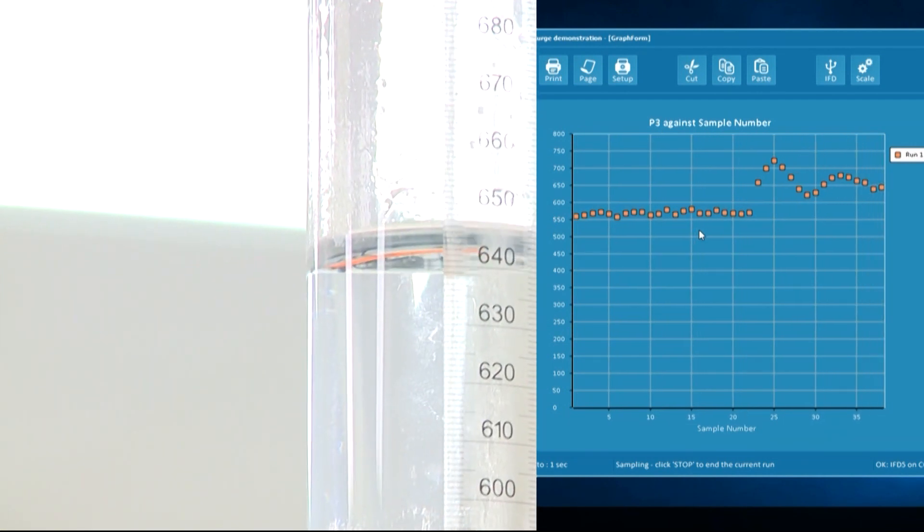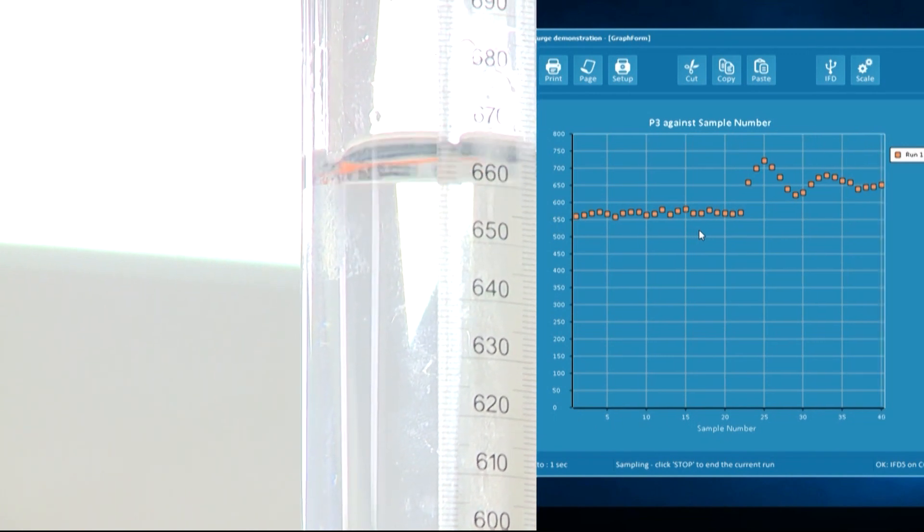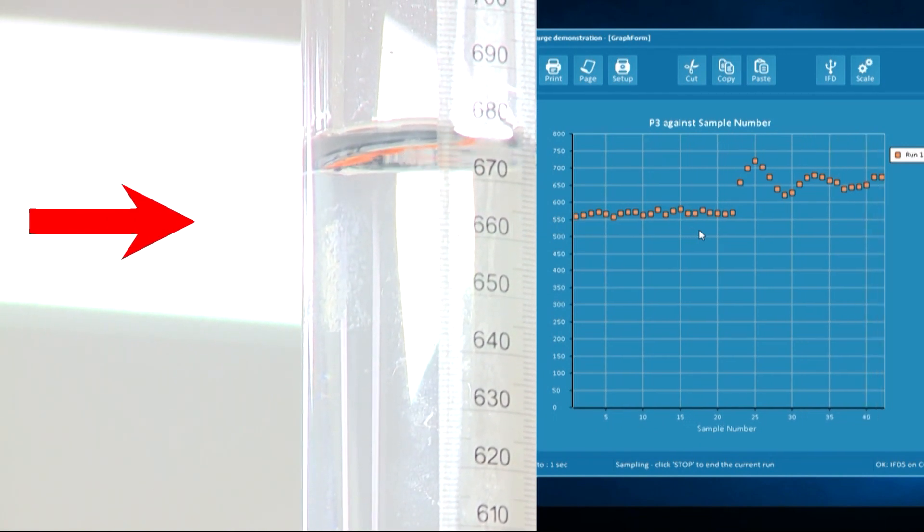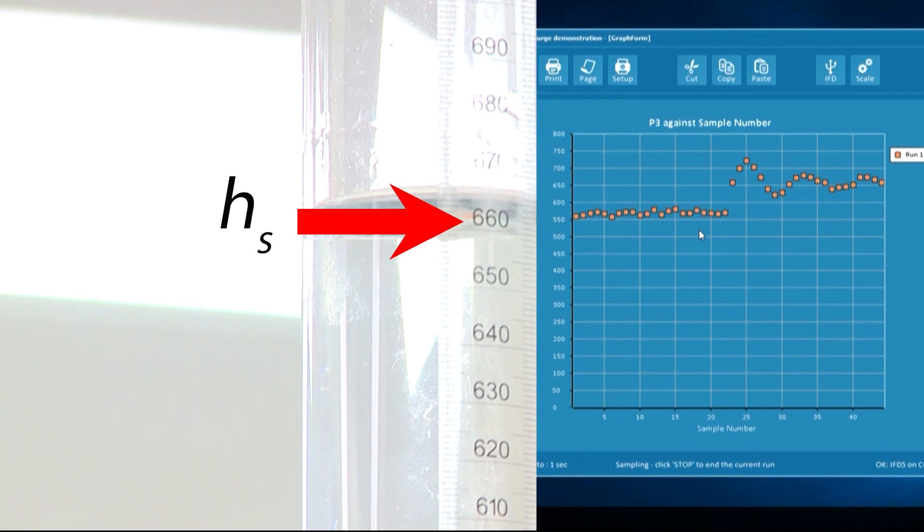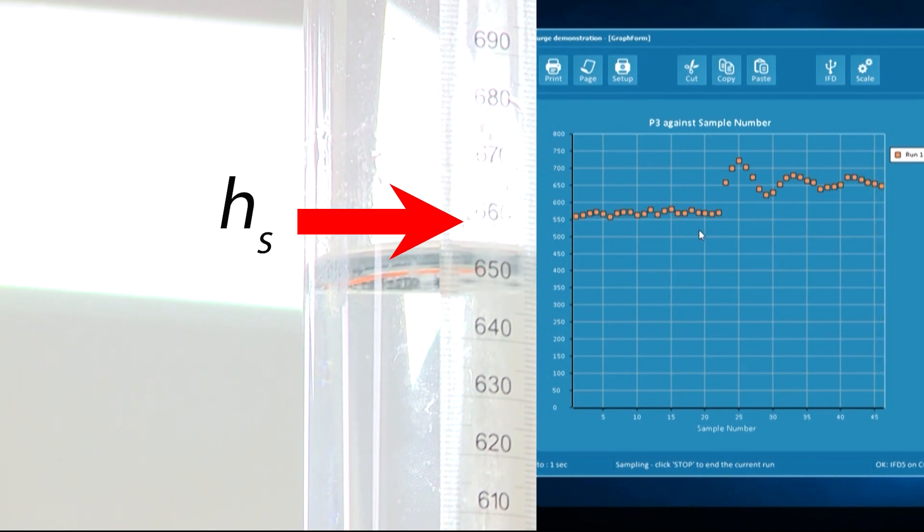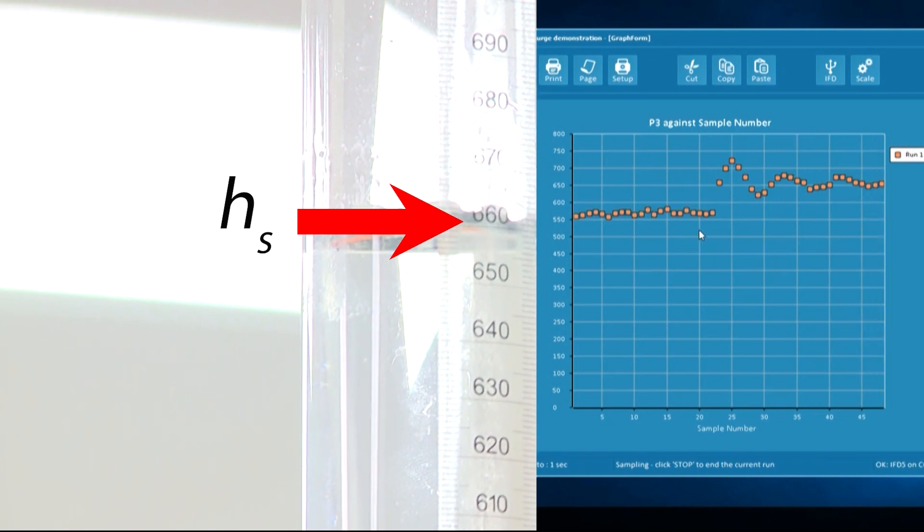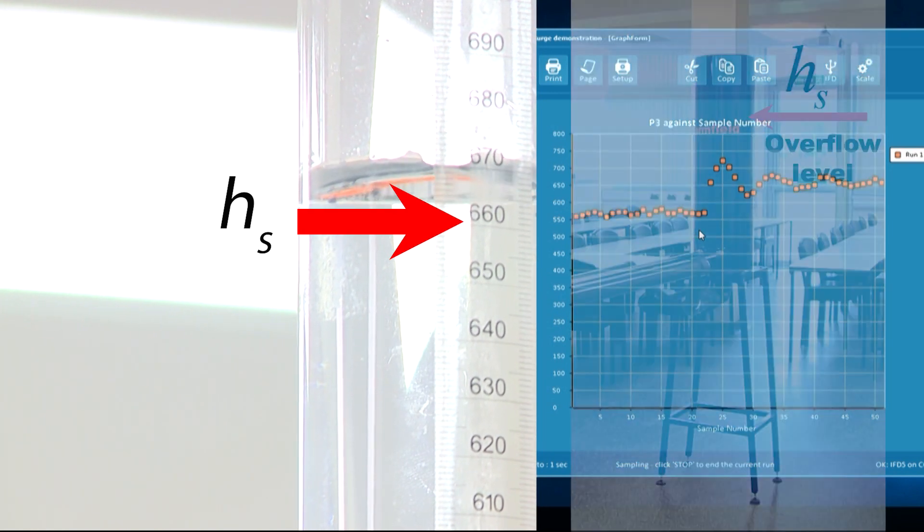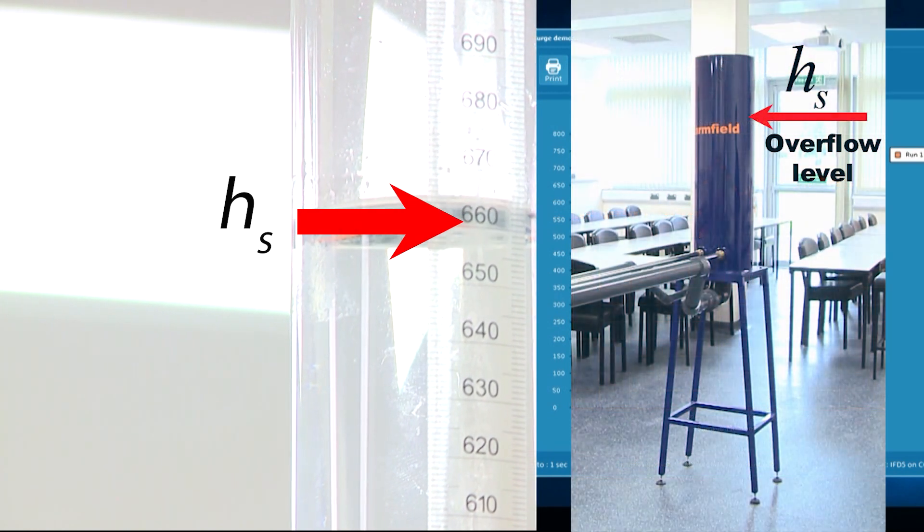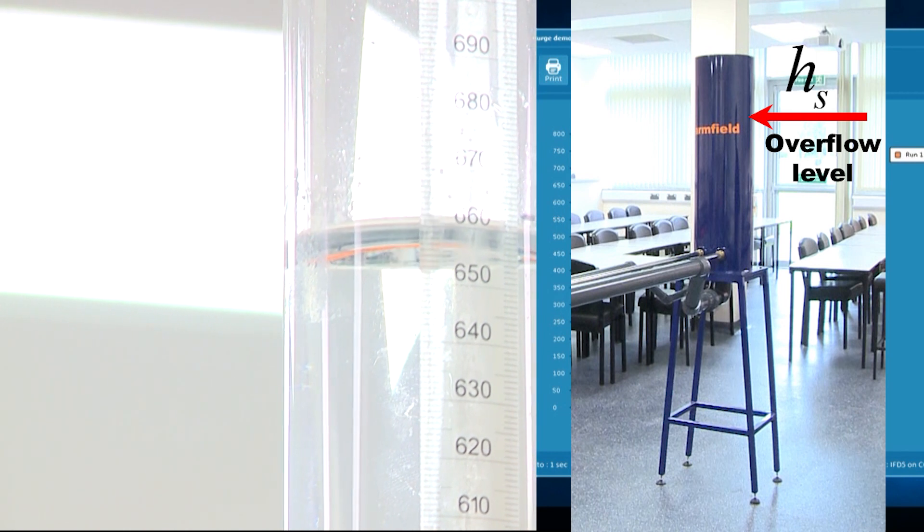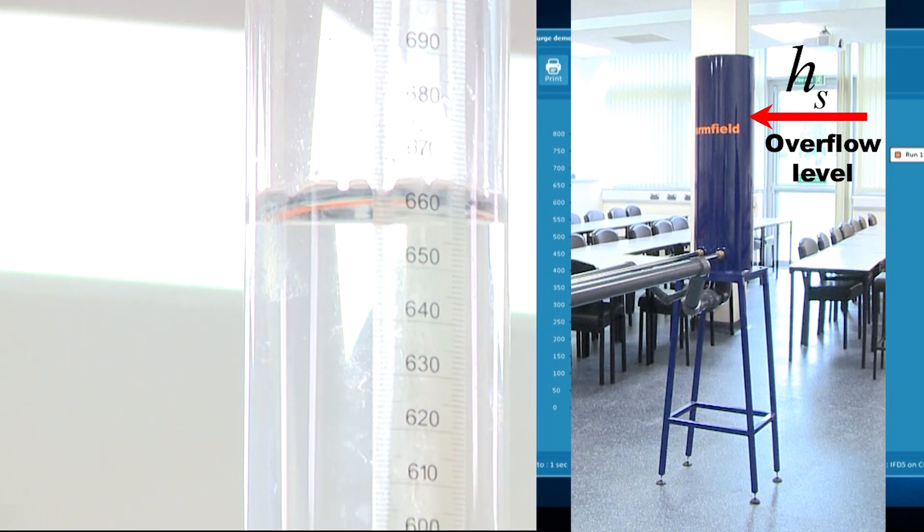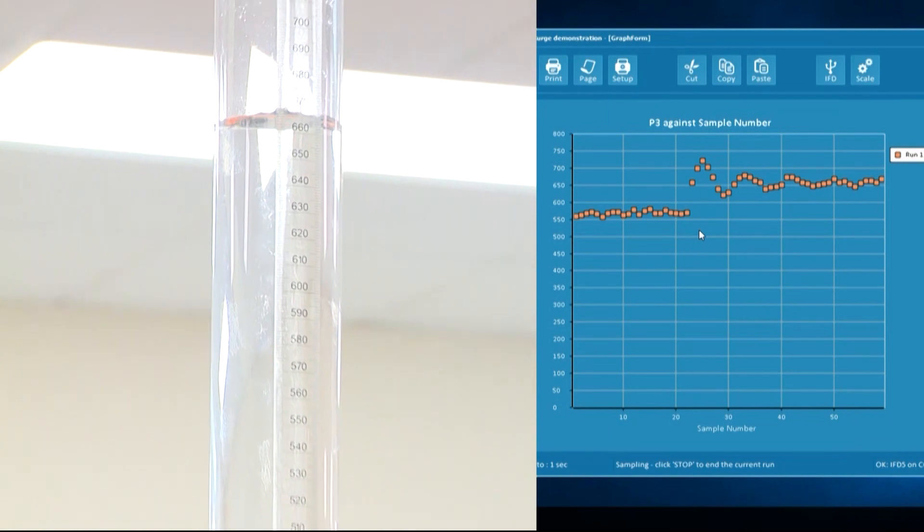We can observe how the water level in the surge tower rises above static level and then falls below the static level. And the level continues to oscillate with reducing magnitude until the level is steady at the static level, which is equal to the overflow level at the header tank.